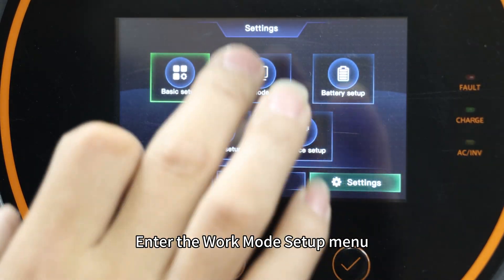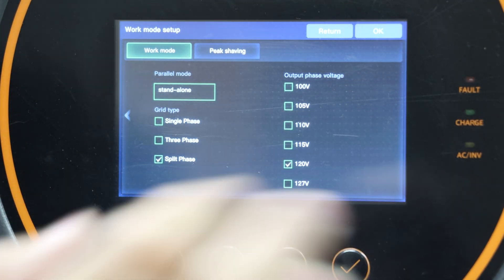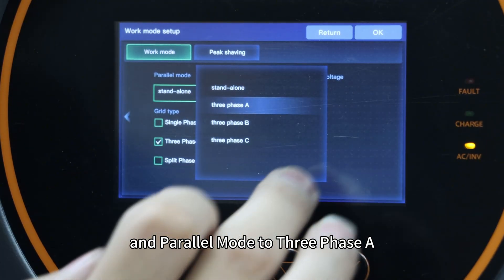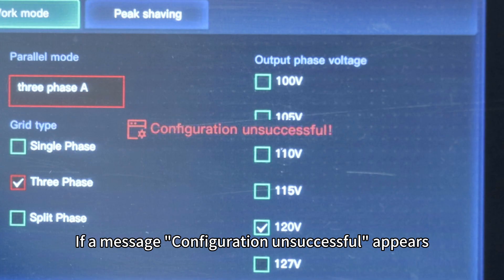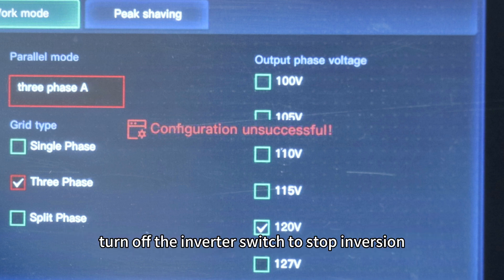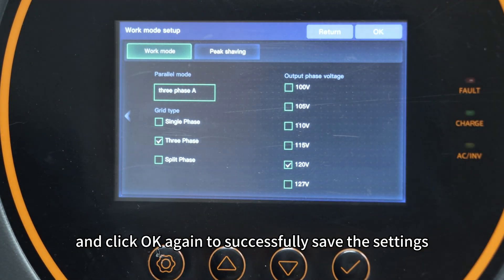Enter the work mode setup menu and press the right key to access the second page. Set the grid type to 3-phase and the parallel mode to 3-phase A, then click OK to save. If a message 'configuration unsuccessful' appears, that is because the inverter is still in inverter mode and the phase setting cannot be changed at this time. To fix this, turn off the inverter switch to stop inversion and click OK again to successfully save the settings.